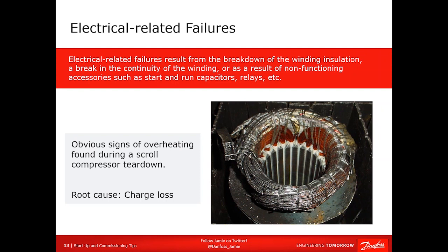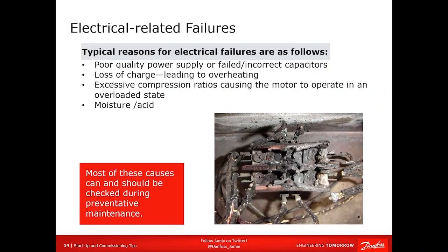This is charge loss. Charge loss is very sinister because your high pressure control will not protect against it. Your superheat goes up, the amount of gas coming back to cool the compressor goes down. Eventually, you will either lose lubrication and seize it, or you will break the insulation in the winding and have an open or shorted winding, one of the two. And these are all images that come back from our teardown analysis.